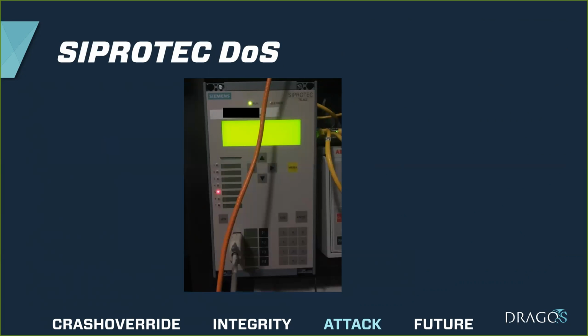It actually triggers a known functionality within the SIPROTEC to put the device into a firmware update mode in order to conserve memory on legacy equipment. As a result, all existing protective logic is wiped, but a cursory glance at the box indicates it's still running—the blinky lights are still blinking, etc. If you're rushing around a transmission plant and just glancing at this, it might look okay. Obviously if you look at the display console there's nothing there, which is problematic, but if you're really rushing to get power up and running as quickly as possible, are you necessarily going to notice this?